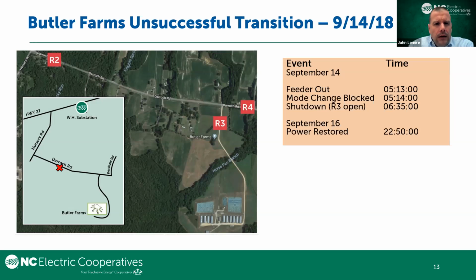That's not what happened. You can see from our event times, we had the feeder go out. The microgrid did not transition, and then, due to the UPS on the centralized controller, the battery being drained, the system shut down. By the time they could get out and clear the tree off the line, it was a couple of days later. So again, we did our root cause analysis to determine what happened.